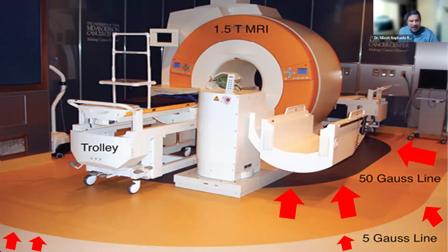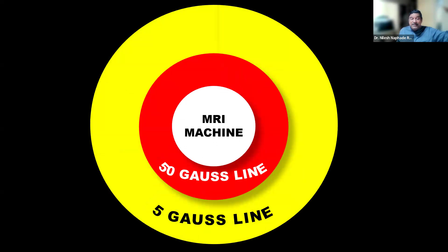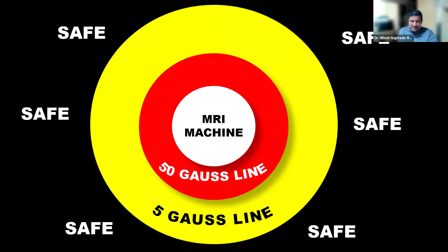To make this a little simpler, if the computer monitor screen you are looking at is the MRI room, and this is the MRI machine, then this red area and the outer border of this red area is the 50 gauss line or 200 gauss line, depending on how big the MRI machine is. And the outer border of the yellow circle on the screen is the five gauss line. So all the areas outside the five gauss line are safe in terms of the magnetic field. We need to understand this because these are the areas where you can take ferromagnetic substances, otherwise not.